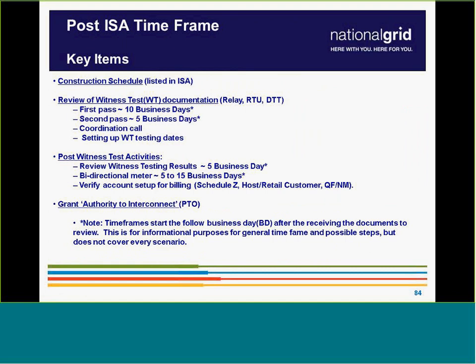For the key items, once results are back we have five days to review, then five to fifteen business days to set the bidirectional meter, though it's usually quick. Once the witness test passes successfully, we schedule the meter set right after, which takes a couple of days. Then we make sure billing is correct and the account is coded. After that, with all final documentation in place, we send the authorization to connect, the so-called PTO letter.